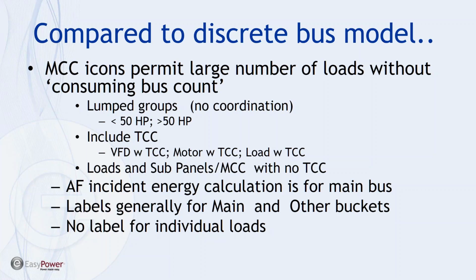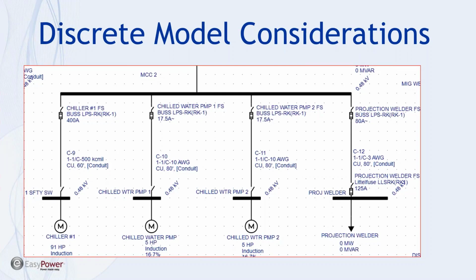However, in a 480 volt system, the labels that are generated are generally twofold. One is for the main bucket, and as long as it's isolated from the main bus, then the labels can be generated for the main bus, which could be applied to the other buckets which represent loads on the motor control center. So the disadvantage is that there's no individual load labels and consequently no prediction for labels on a motor control center load, which may be at a distance from the motor control center. Both of those can be addressed or overcome by utilizing discrete modeling of my load system and just referring to that as a motor control center type of bus.